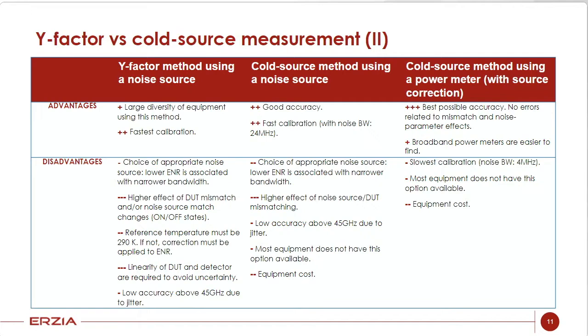In the second column, we have the cold source using the noise source. So the advantages are that the accuracy is very good and the calibration is fast. The maximum noise bandwidth we can use is 24 MHz. The disadvantages are in common with the first column because we are using the noise source. So we have the problem of the choice of the noise source, then the effect of the noise source and the DUT mismatching, also the low accuracy due to the jitter, and we have two new disadvantages related to the equipment. Those are that most equipment does not have this option, and the second one is the price.